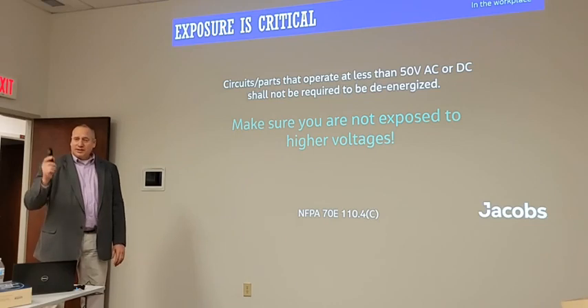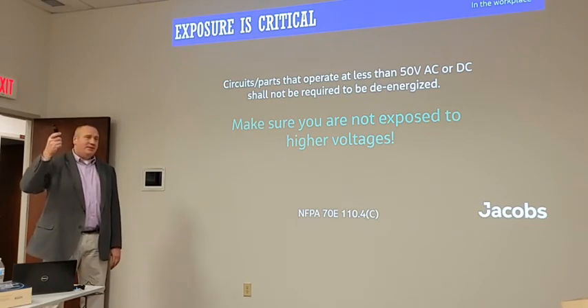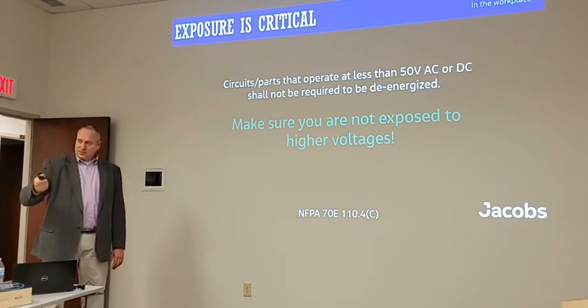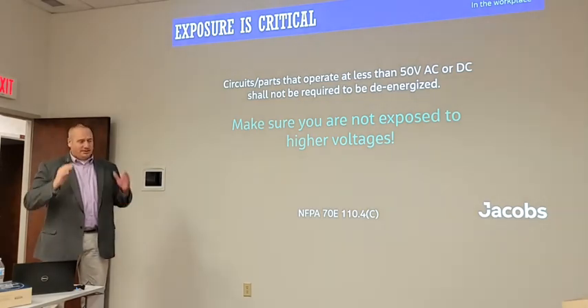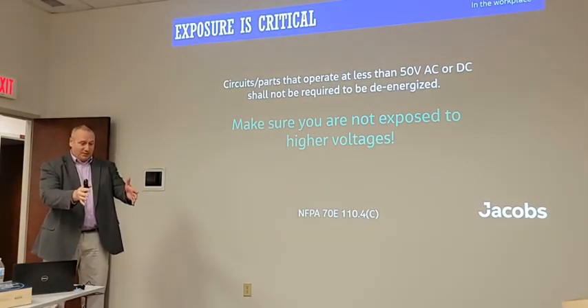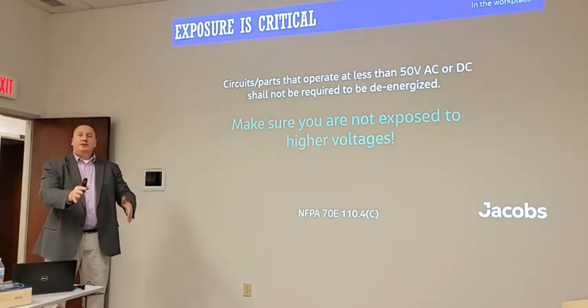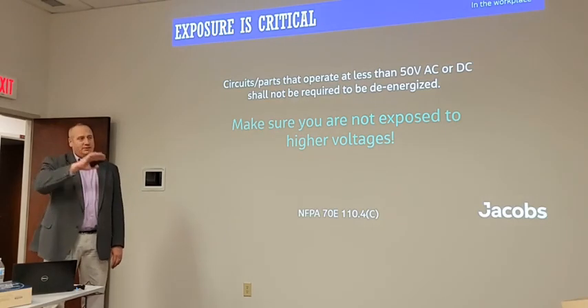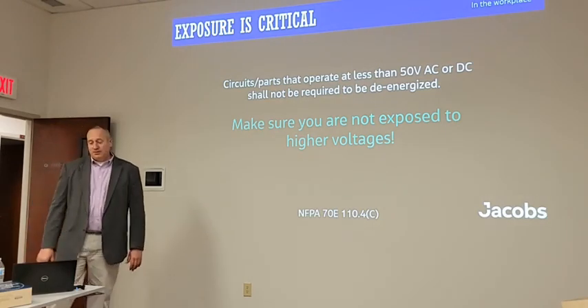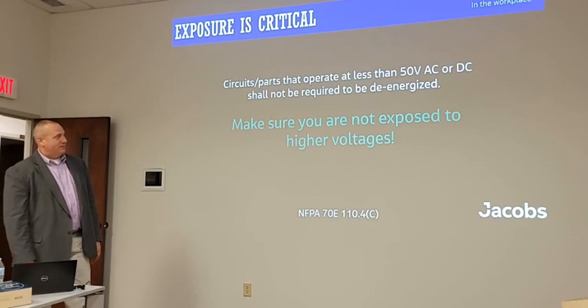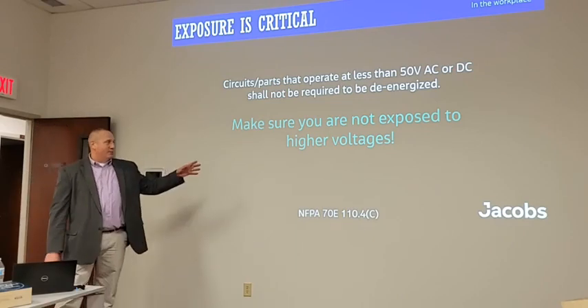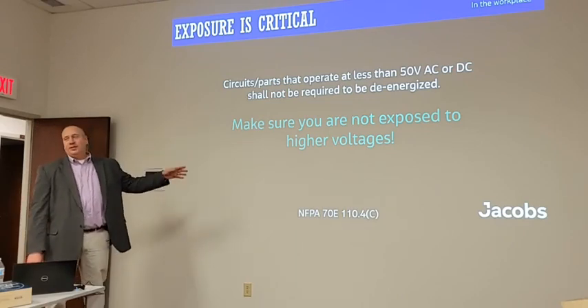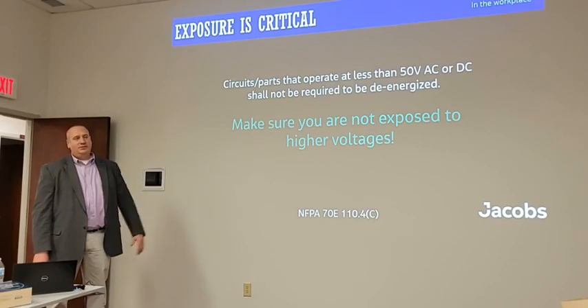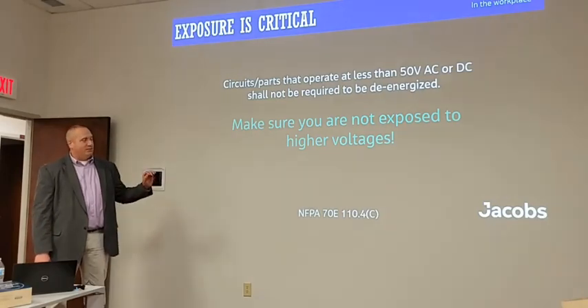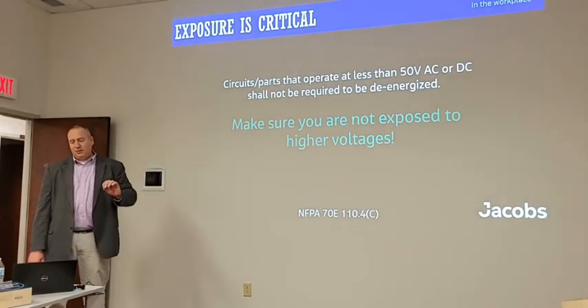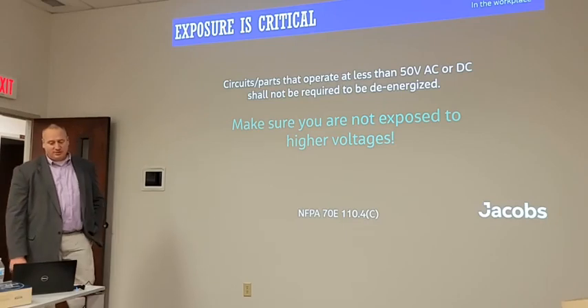And I'm like, you realize that's a 480 volt PT that's in the corner there? And these are 480 volt terminal strips, and not realizing the blinders are on, that this is what I'm working on, and it's not a hazard. And that's true, but when you open that enclosure, you're exposing yourself to a potential arc flash hazard because of that exposed 480. So changing the mindset of not just what am I working on, but what am I exposing myself to? And that's the thing that we've got to protect ourselves, not what we're working on, but what we're exposed to, the hazards that we're exposed to.